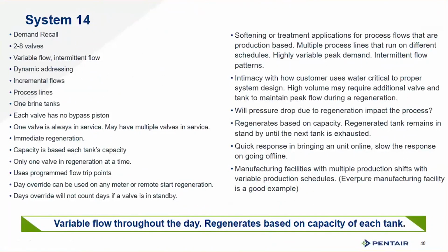System 14, this is demand recall. This is for multiple variable flow rates throughout the day, multiple equipment lines being brought on and off with shifts. So you don't have a real good idea of how much water you're using when. Hotels, this is a great application for this. So anybody can use water when they want, and the softening system will keep up. It'll pick up flows and bring another one online to manage the increase in flow and then step back down when flow rates drop. This is really good in those hard to manage flow rate situations. We've got a triplex in our Hanover Park plant to manage the can washing lines. As lines are brought on, we have more softeners brought on and then step down as they go down. So lots of use for System 14 in multiple line manufacturing facilities.